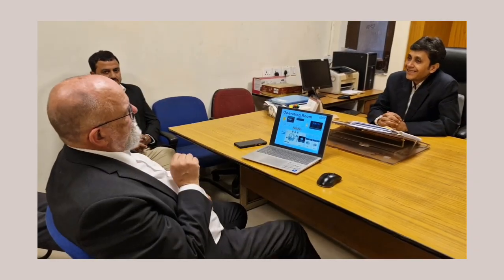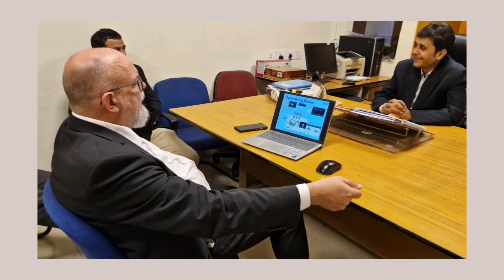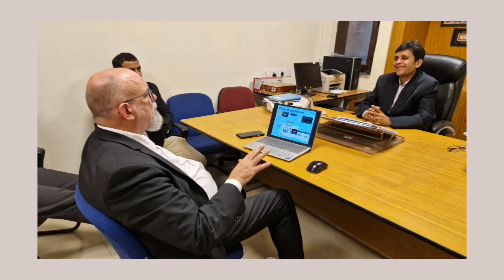No, not really. The maintenance person is outside the ICU because the IT system is installed outside. But he can call inside the OR or the ICU and ask the nurse, what did you just do? I entered the infusion pump in this socket. Take it out, and the fault is gone. This is exactly the point where the maintenance people and the nurses come together and where we can help make the system in the hospital much, much safer. When that operation is over, the maintenance person can enter the operation theater and get it rectified. Exactly. Good.